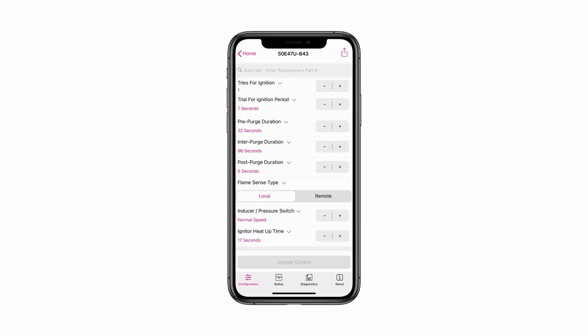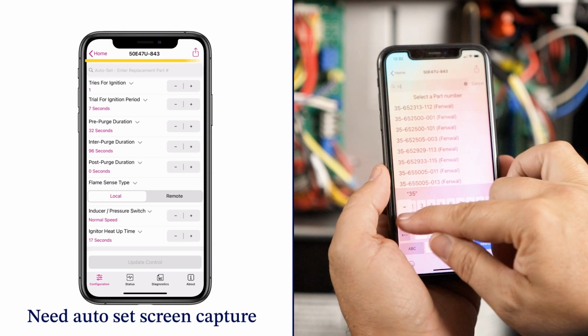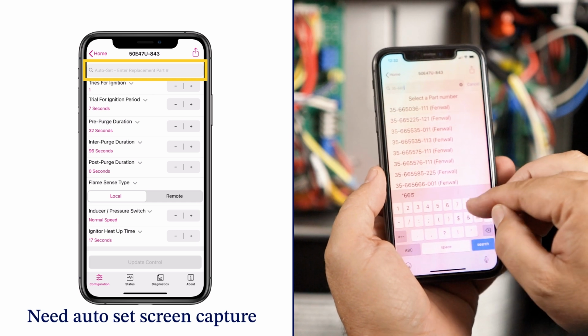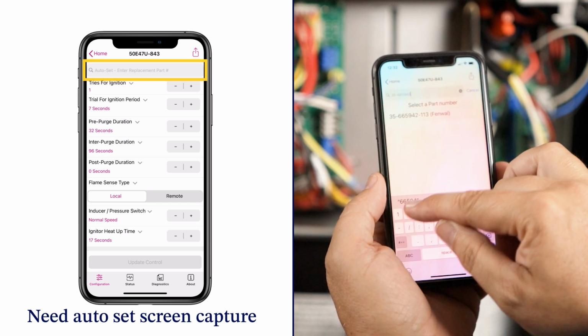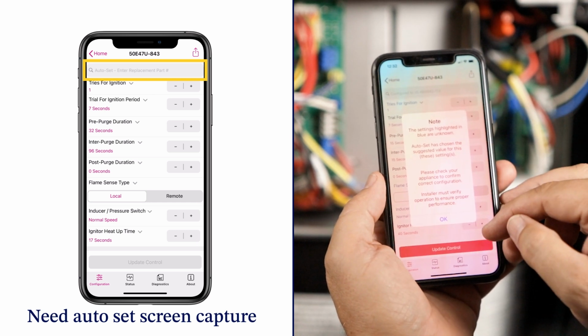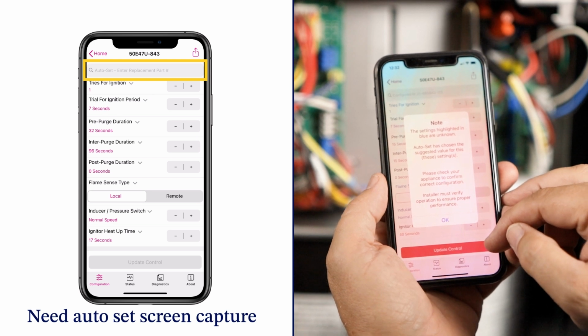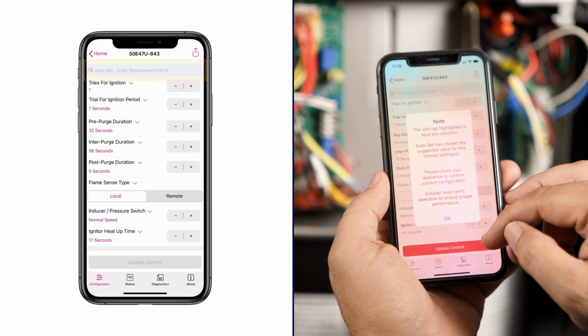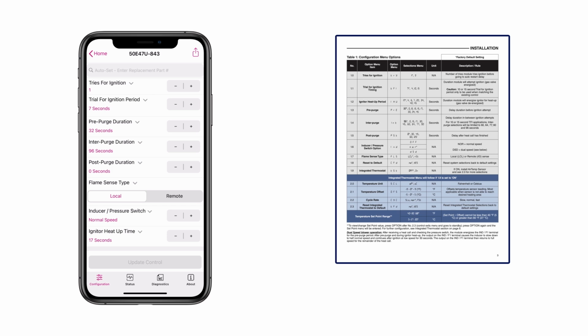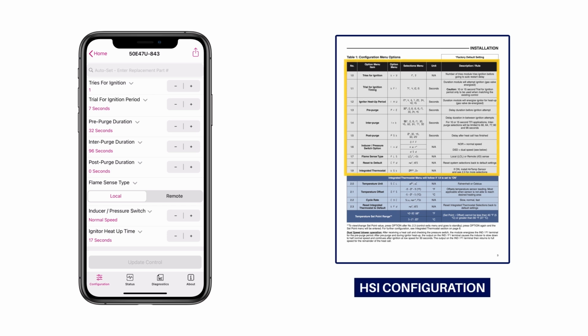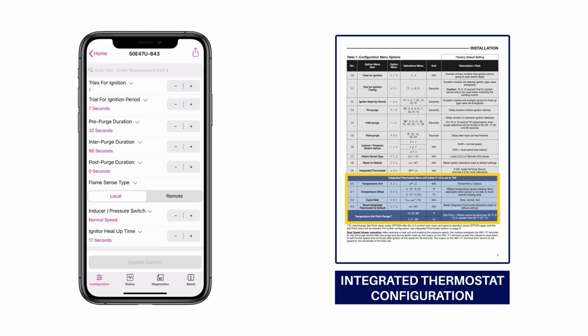The app then displays the 50E47U-843 setting configuration screen. The app has been preloaded with hundreds of OEM control settings. Type the replacement part number into the Auto Set box. This feature will automatically configure the 50E47U-843 to the replacement part's original default settings. Table 1 on page 3 of the installation instructions shows configuration options. Also included are the configuration options when utilizing the integrated thermostat.